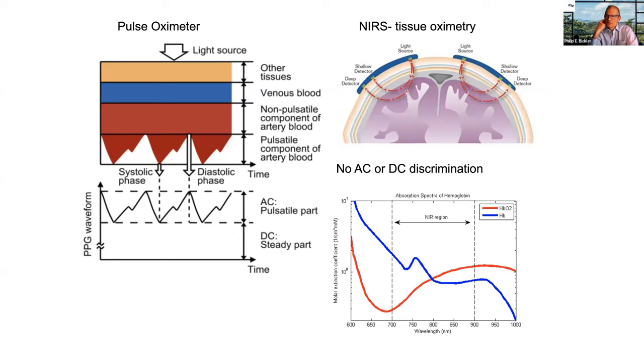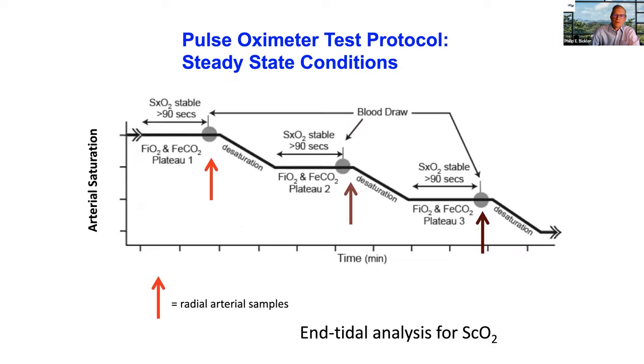You can differentiate pulse oximetry from infrared tissue oximetry, as shown in the figure, where no pulsatility is involved and longer wavelengths of light are used. So with a typical infrared tissue oximeter, there's only infrared wavelengths, which penetrate tissue better, but there's no pulsatile signal involved in the analysis of tissue oximetry values.